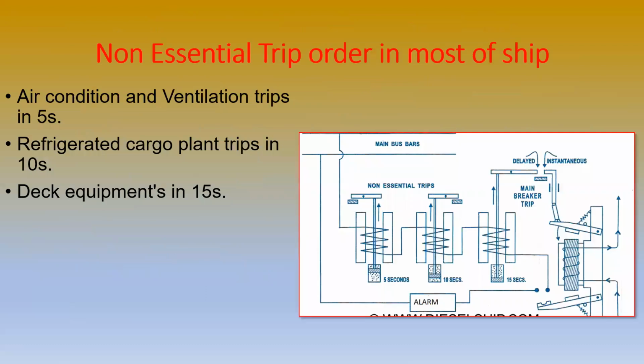This is the non-essential trip order for most ships. In most ships, within 5 seconds the air conditioning and ventilation will get tripped. Within 10 seconds, the refrigerated cargo plant trips. And within 15 seconds, the deck equipment will get tripped. So this is the working principle of the preferential trip.